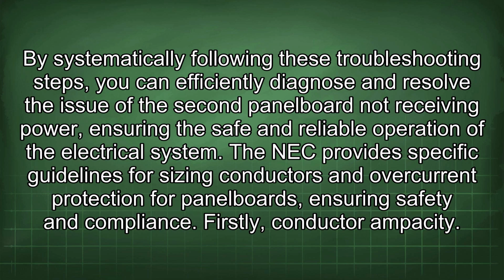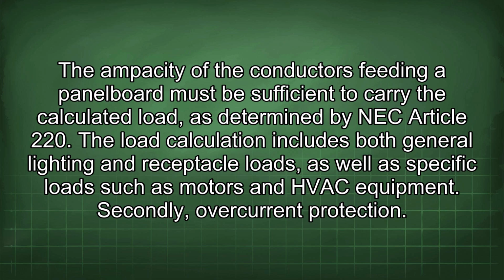Firstly, conductor ampacity. The ampacity of the conductors feeding a panel board must be sufficient to carry the calculated load, as determined by NEC Article 220. The load calculation includes both general lighting and receptacle loads, as well as specific loads such as motors and HVAC equipment.